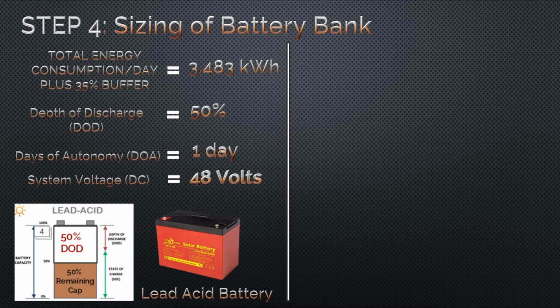Now we have all the needed parameters to compute the size of a battery bank. In this example setup, I will use a lead-acid battery in our computation. But if you will compute for a lithium-ion battery, just change the value of DOD in the formula that you will use. So this deep cycle lead-acid battery has a DOD of 50%, and we use 1 day of autonomy, and the DC system voltage is 48 volts.